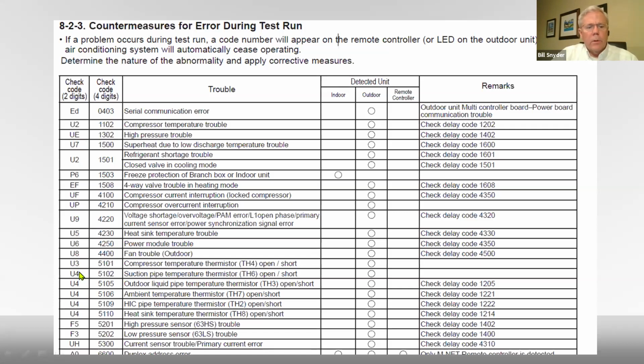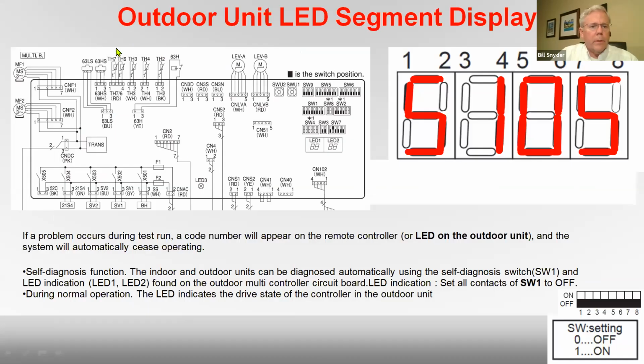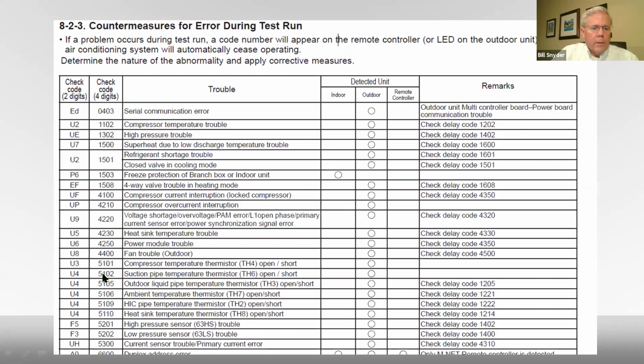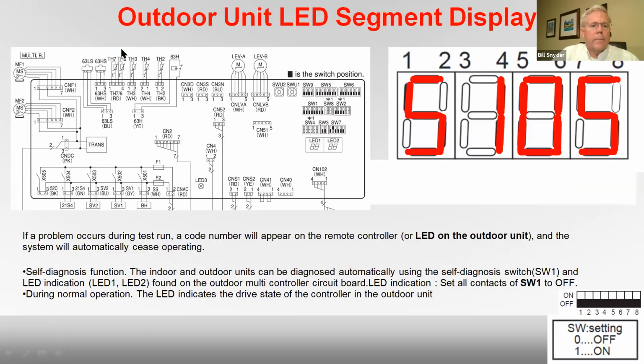So it would tell you that you've got to check your thermistors, which are right up here on the board. Remember, we had a 5105. If we go a little bit further to 5105, it's U4, which is the thermistor, and it's telling you your outdoor pipe thermistor, your liquid pipe temperature thermistor, TH3, is open or shorted. If we go back here, these are your thermistors. TH3, which is a white connector, there's a problem with.